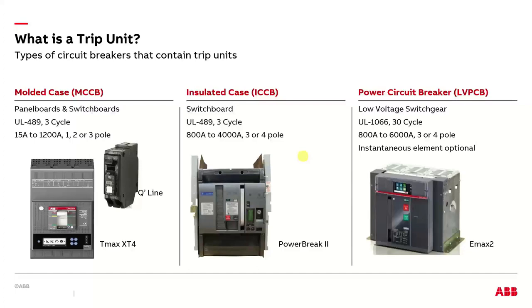Then there's your insulated case breaker, which is kind of a hybrid between a power circuit breaker and a molded case breaker. It's meant to have no serviceable parts, similar to the molded case breaker, but it's a higher power rated breaker, and more importantly, it's a stored energy breaker, where you charge a spring and you can take multiple open and closed cycles with the spring charge. Whereas a molded case breaker has a single trip spring, so when you set it and it trips, that's it, and you don't crank a handle to charge it. In the insulated case, this handle here is what you pump 6 or 7 times that charges up the springs. That's very similar to a power breaker, so it's this interesting hybrid that sits in between.